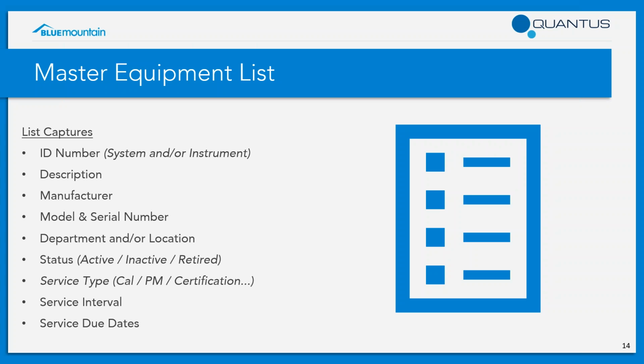Boilerplate data such as manufacturer, model and serial number, department and location are a critical parameter. We typically also like to see status on your master equipment list so that you can tell very quickly if a particular piece of equipment is active, inactive, or in a retired state. And finally, one key piece of information is your service information. The service type, interval, and due dates are all very important information you should be able to pull very quickly from your master equipment list.